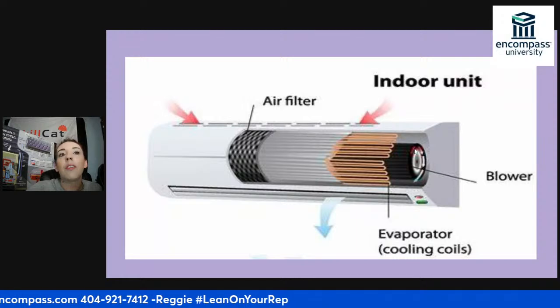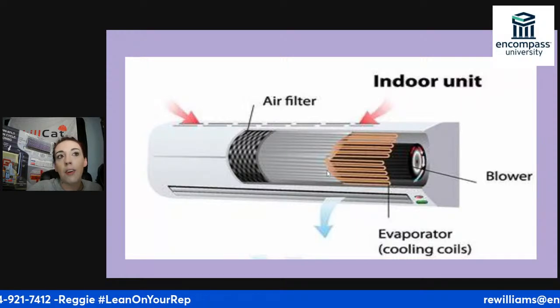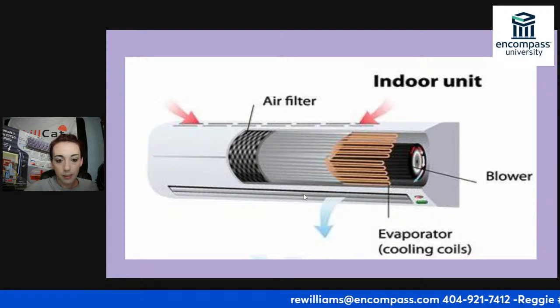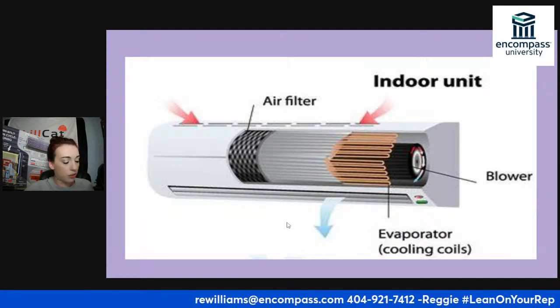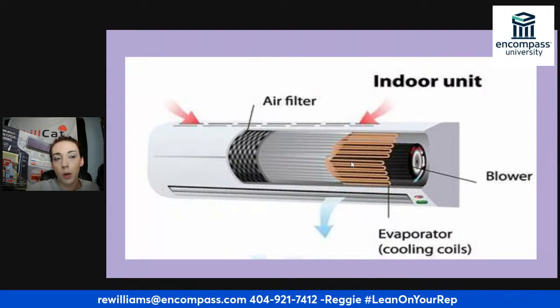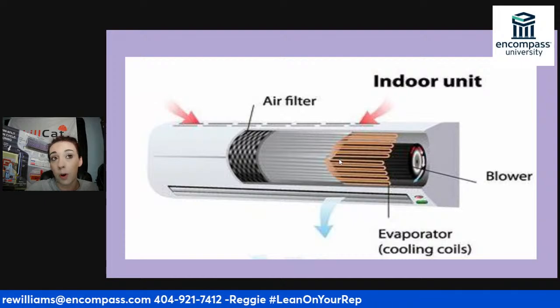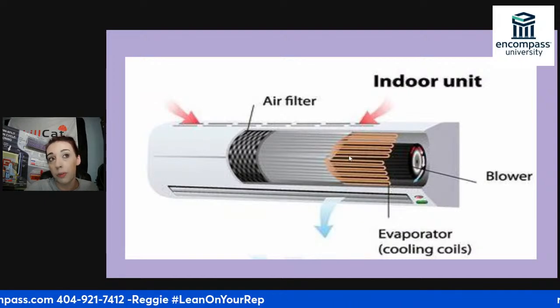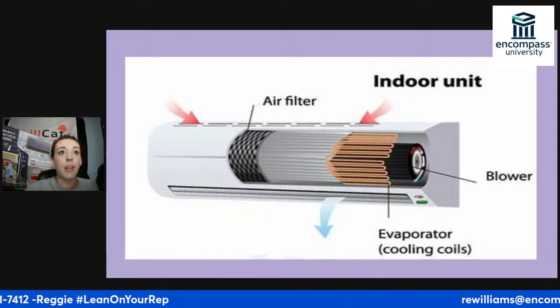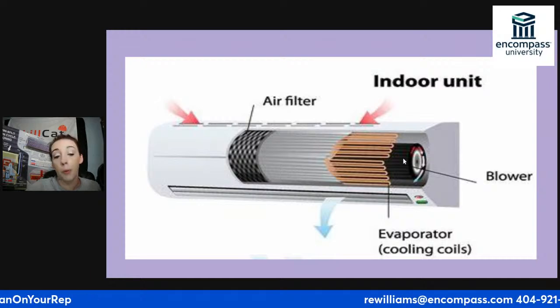So when this wheel is spinning, everything coming through this coil, I don't know if you guys can see my cursor, but everything coming through this coil is not only getting trapped in the coil, but whatever doesn't get trapped, see between these coil loops, lots of things escape. And the things that escape get caught on the blower wheel.